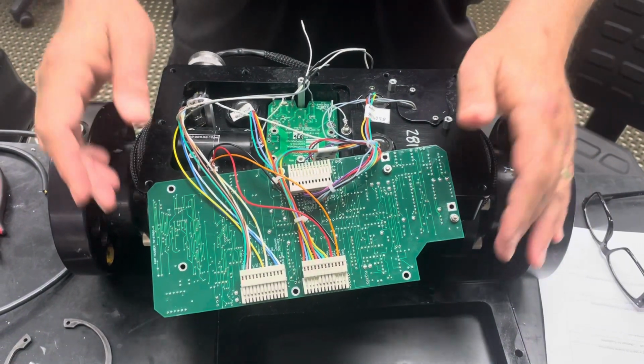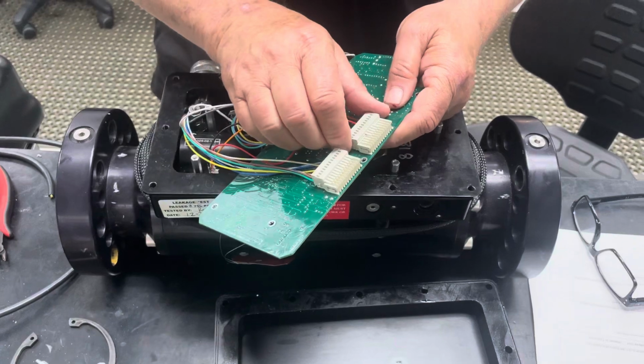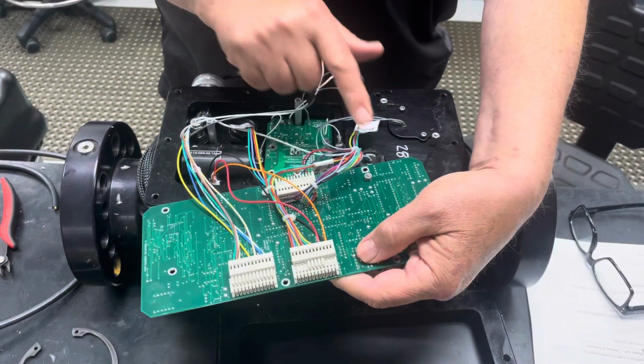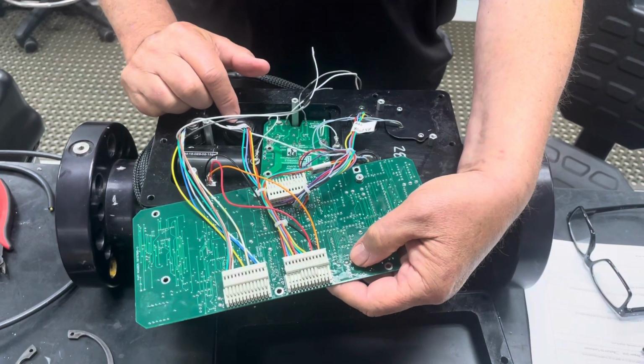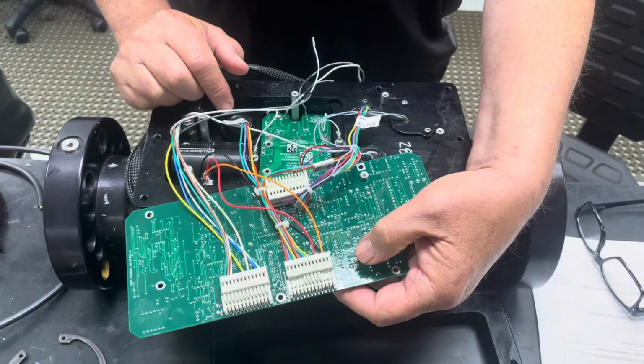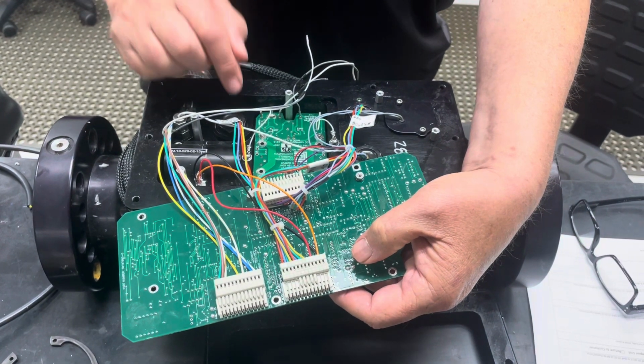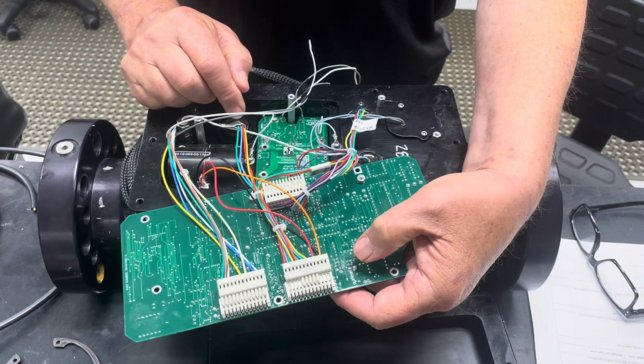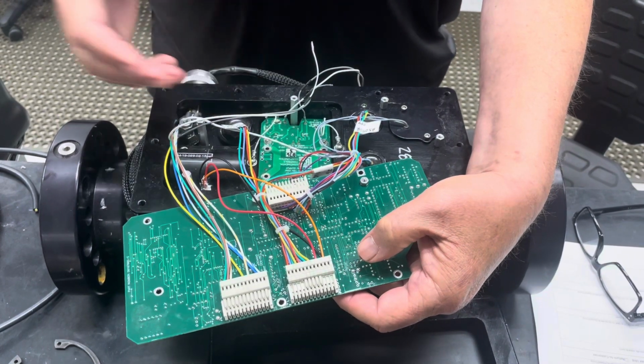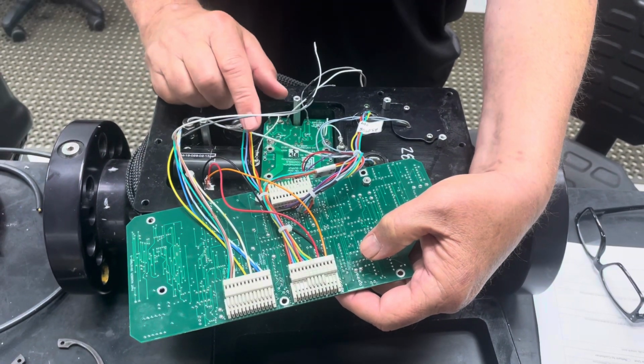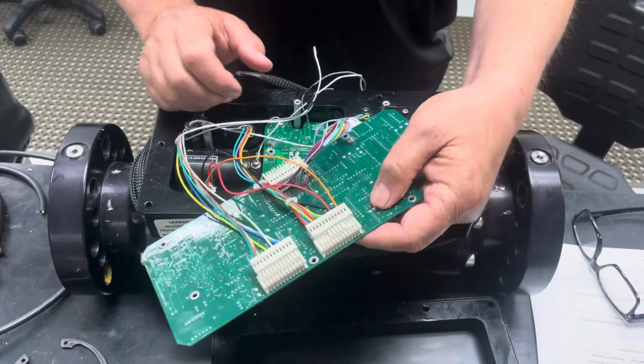Now the other thing you need to be aware of is that these wire colors are all the same. If you have an older valve or a valve of a different configuration, the transducers will not be interchangeable. But if the wire colors are all the same and you have two similar valves, you should be able to swap the transducers.